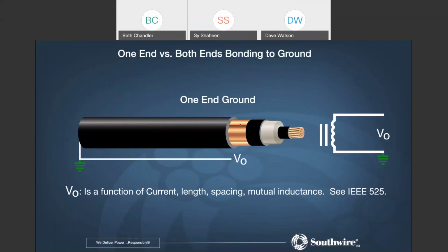A lot of times I'm asked as an engineer, well, when we terminate the medium voltage cable, should we terminate it at both ends or not? Should we ground it at both ends or not? Here's a cable. Imagine this end is at the switch house. This end is inside of the data center area. Again, you have to go through the turnstile to get in there. This is outside, on the switch yard, where the utility feeds it. Well, should I ground it at both ends? I have a termination here.